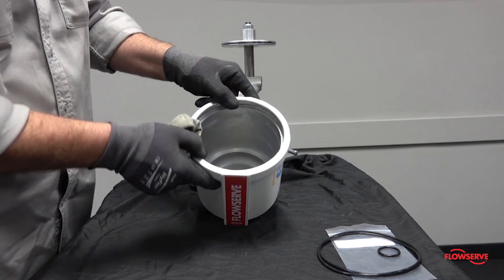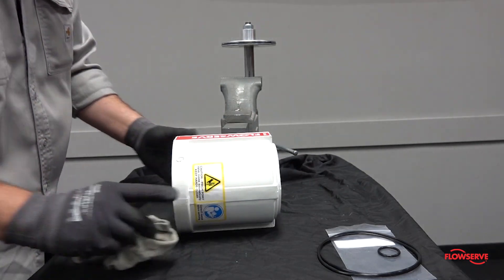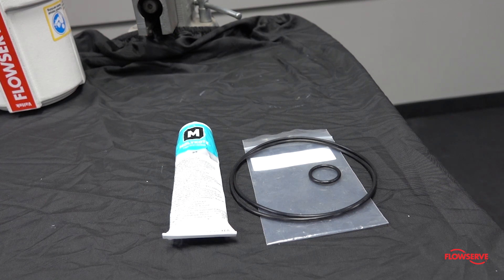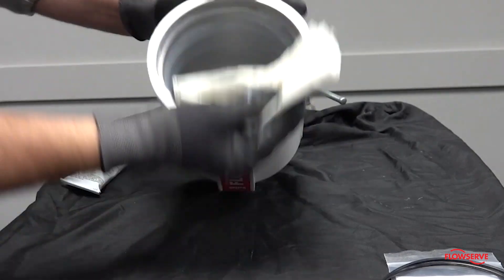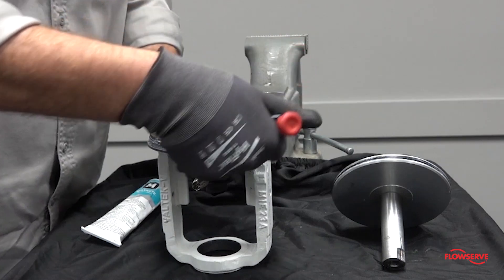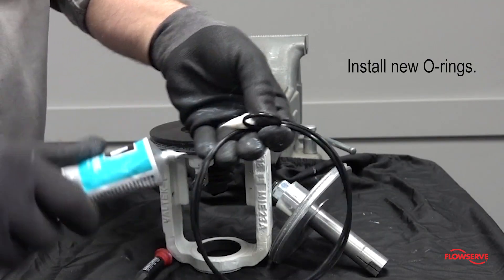It is recommended that the old grease be wiped out of the cylinder and that the internal surface be inspected for damage. If damage is noticed, the cylinder should be replaced. It is also recommended that all soft goods be replaced and lubricated with Dow Molykote 55 grease when reassembling the actuator. Apply a thin coat of Dow Molykote 55 grease to the inside of the cylinder and place the cylinder upside down for reassembly. Remove the o-rings from the yoke bushings, yoke to cylinder seal, and the piston o-ring. Lubricate and install new o-rings.